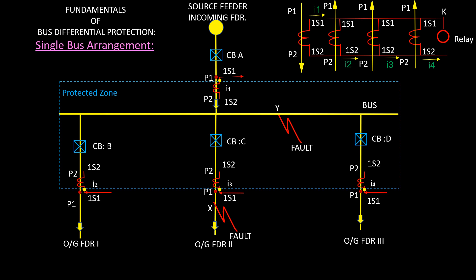Suppose a fault occurs at feeder number 2 at point X, outside of the protected zone — a through fault. Circuit breaker C will trip and the other feeders will remain active normally. But if circuit breaker C does not trip, then it will be regarded as a bus fault. Due to fault on bus, all circuit breakers connected with that bus are made to issue a mandatory trip after the shortest time delay. This is known as LBB — Local Breaker Backup Protection.